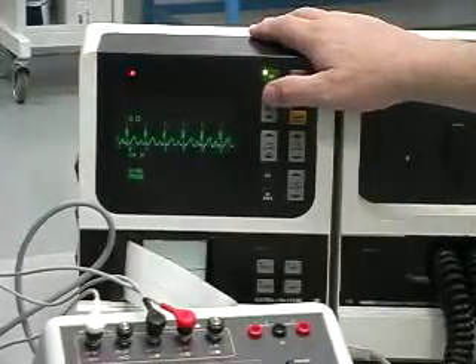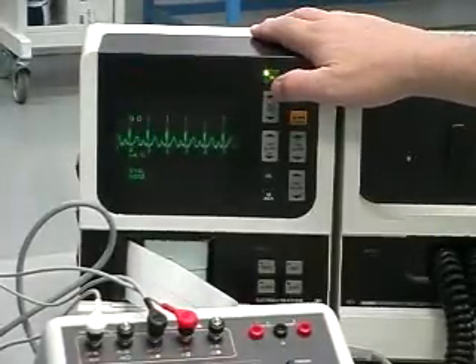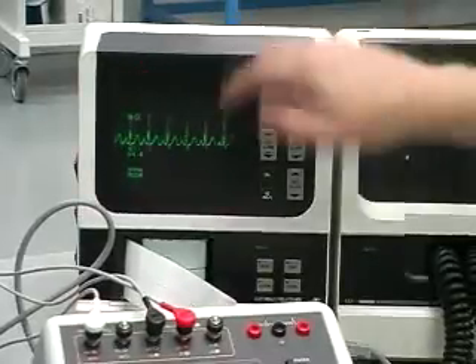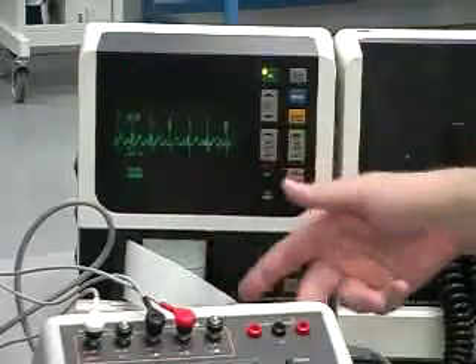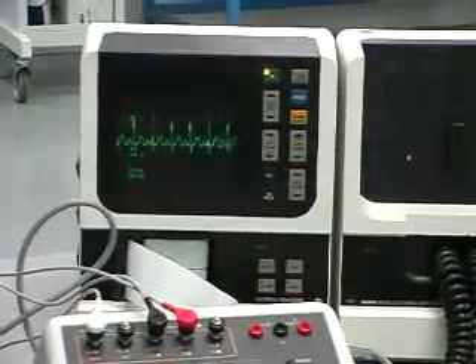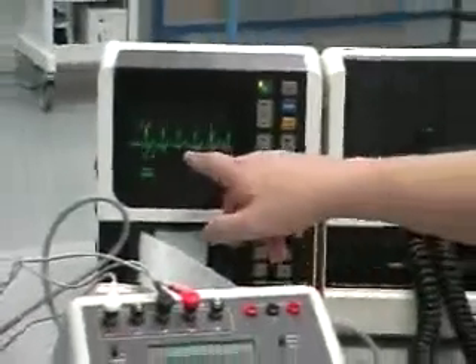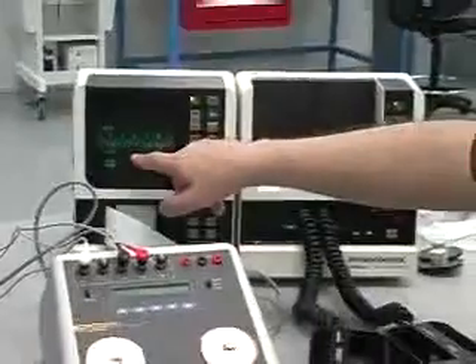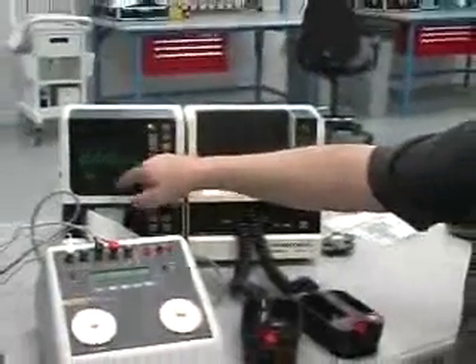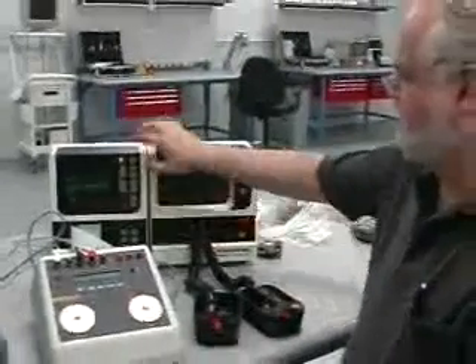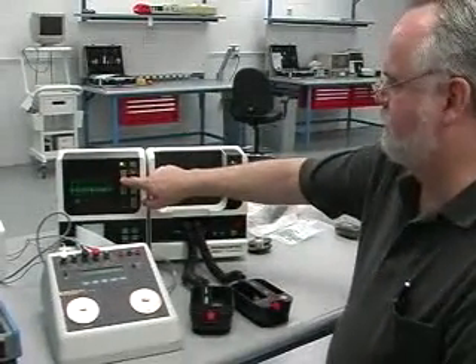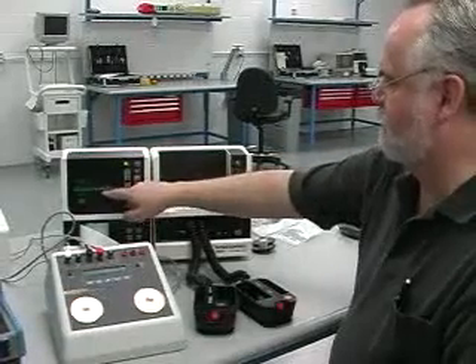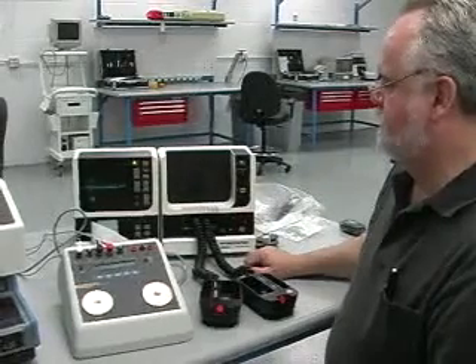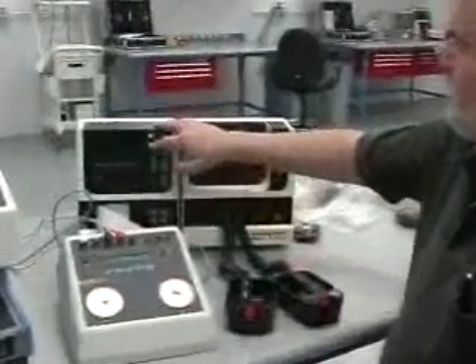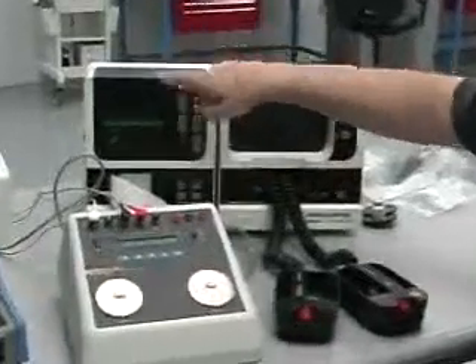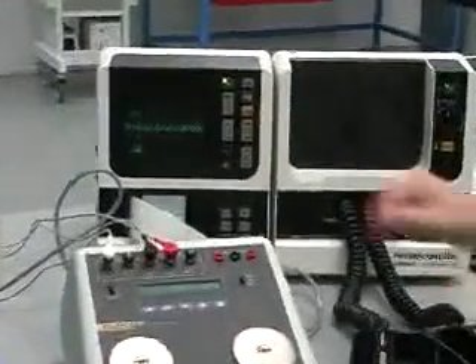So if we were to pop up the amplitude a little bit, okay, then it is getting it on the leading edge most of the time on the ECG. So just as long as it's not down at low amplitudes or negative, or not on the P wave or obviously the T wave. And again, regardless of the settings, it's still going to be somewhere typically within the R wave complex. So at the lower amplitudes, we seem to be getting a good indication, except for when I mentioned it. So that looks pretty good.